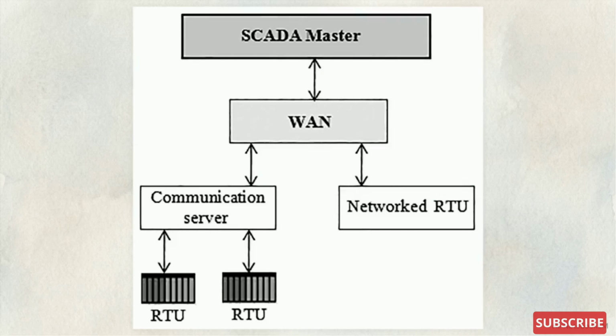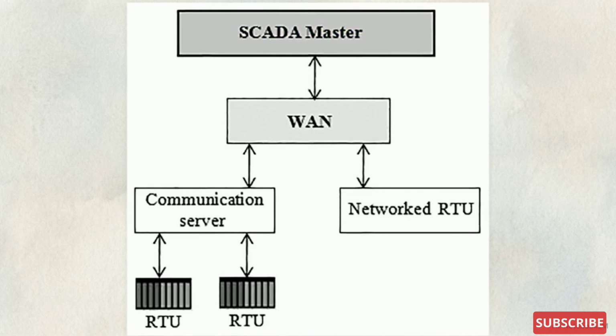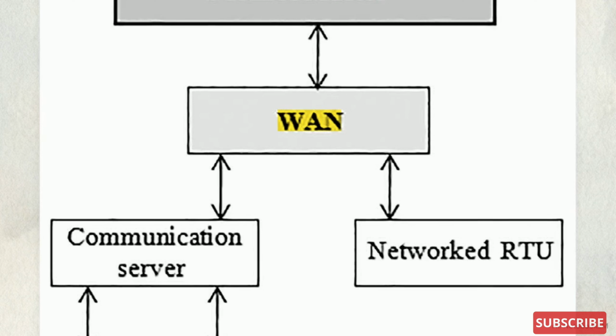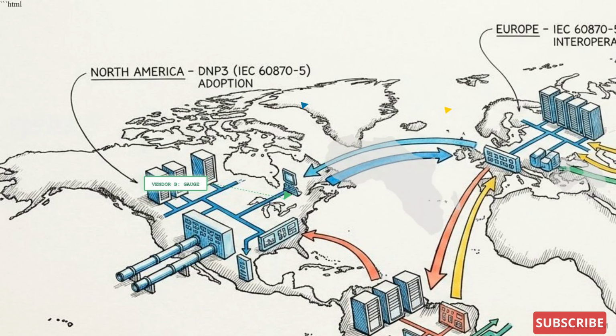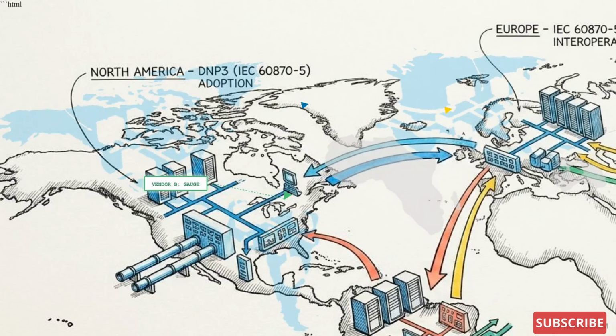As industrial automation scaled up, the industry demanded open system architectures. This drove the third generation, networked SCADA. Proprietary links were stripped out and replaced by wide-area networks. True hardware interoperability became possible through the adoption of open protocols, primarily DNP3 in the Americas and Asia, and IEC 60870-5 in Europe. A device from one manufacturer could now seamlessly replace a device from another.